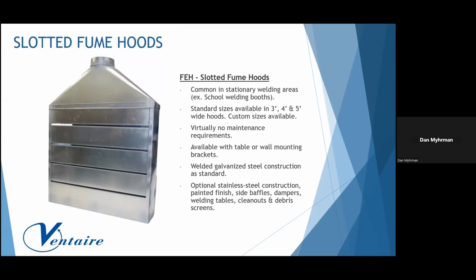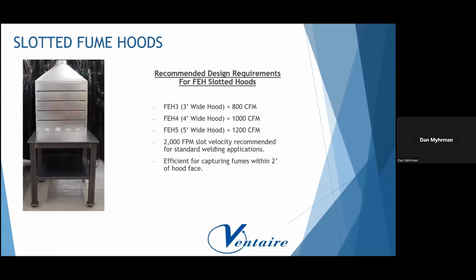Standard construction is galvanized, but we can offer them in stainless. We also offer a few accessories for our slotted hoods, like side baffles to increase capture velocity, dampers, welding tables, cleanouts. Recommended design for our standard FEH hoods: the 3-foot wide hood, about 800 CFM each. 4-foot wide, about 1,000 CFM. 5-foot wide would be about 1,200 CFM. Typical slot velocity is about 2,000 feet per minute.